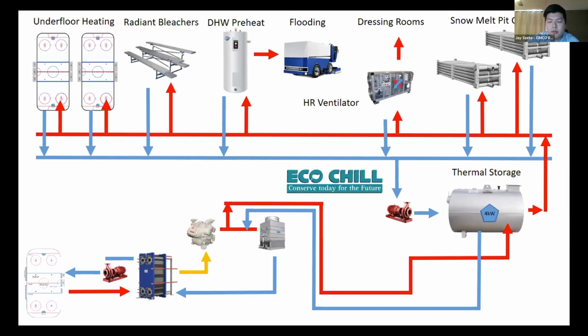But let's assume the dressing rooms in your facility are dropping in temperature and require heating. The integrated control system with the VFD pump can circulate that waste heat throughout the dressing rooms and bring that temperature up. However, if everything's connected to the system and calling for heat, it can provide that demand from this thermal storage tank. So you can see it goes to their underfloor heating, radiant bleachers, domestic hot water, dressing rooms, and snowmelt pit.